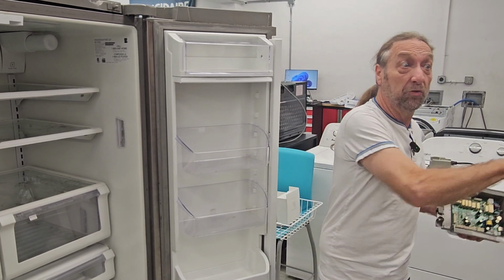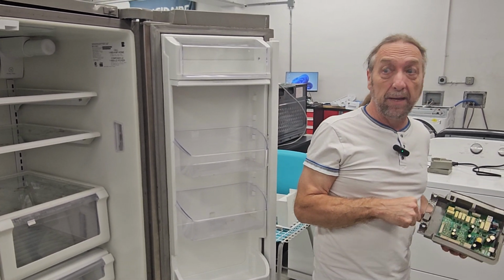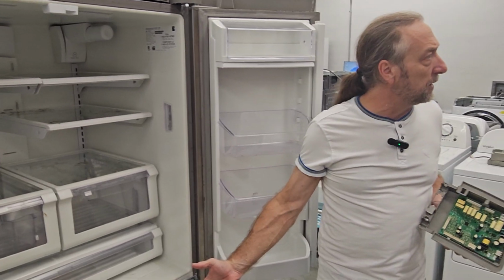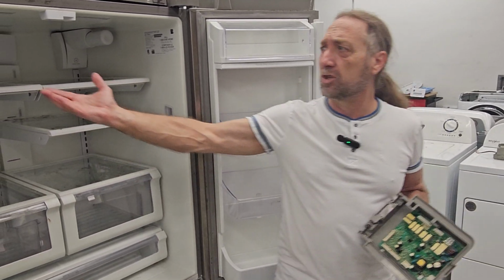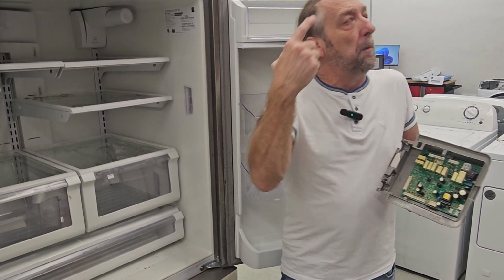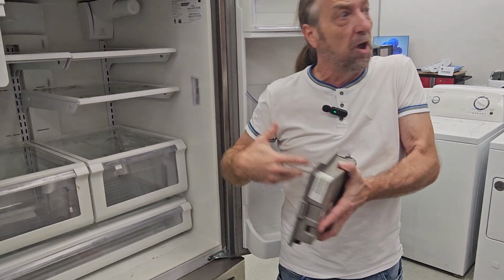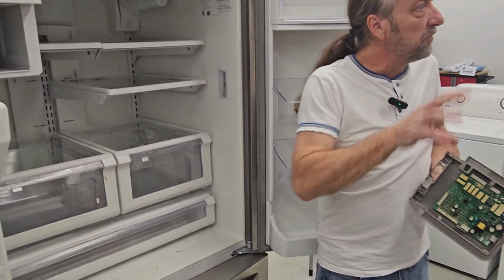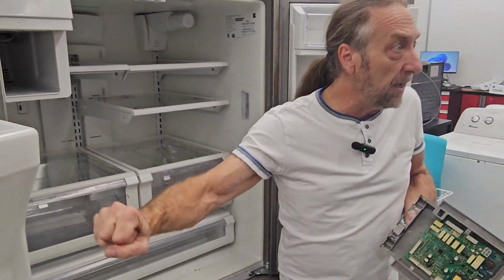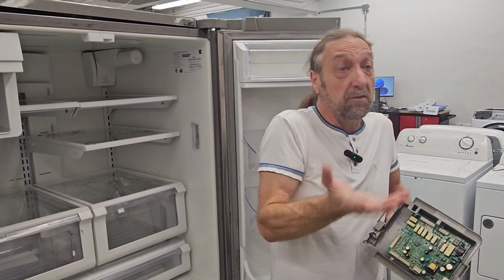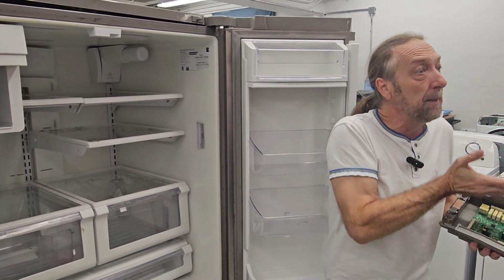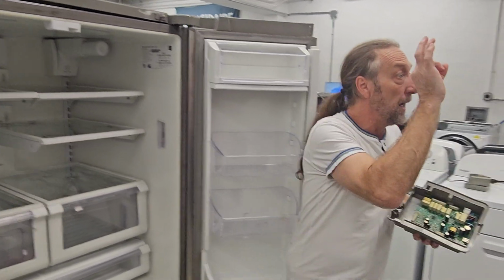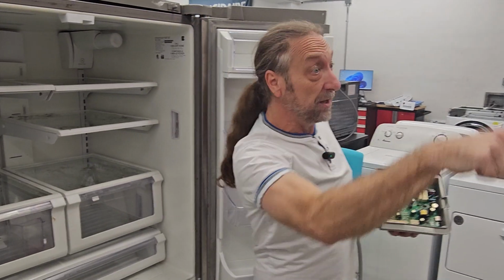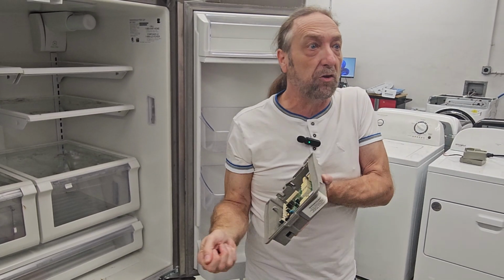When you go to a machine and you're not comfortable troubleshooting it, you start testing things you know how to test and eliminate them as possible problems. If I go to a refrigerator that's not cooling, am I going to check a water valve or the ice maker? No. I know what components I need: compressor, fan motors, defrost. So I test the condenser fan motor, the evaporator fan motor, or just look to see if it's working. You have to eliminate. If you know the problem is in a certain circuit, you just check that circuit.